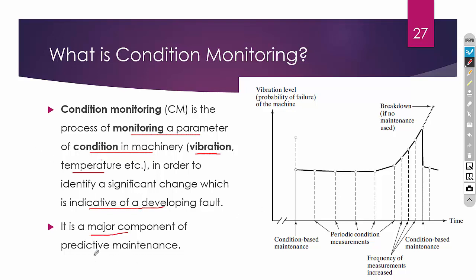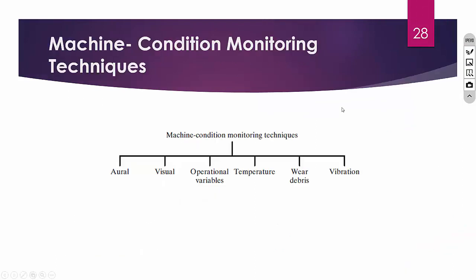Condition monitoring is a major component in predictive maintenance. Looking at the maintenance chart, the x-axis shows the lifetime of the machine and the y-axis shows vibration levels. For some time vibration levels will be low, but eventually they start to increase. Using condition-based monitoring, we can identify that vibration levels are getting increased and rectify the fault to avoid unwanted breakdown. Without condition-based maintenance, vibration levels will increase and damage the overall system.